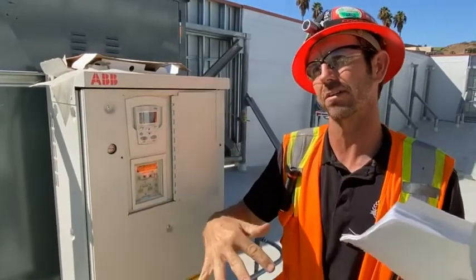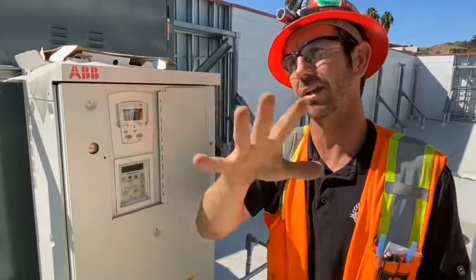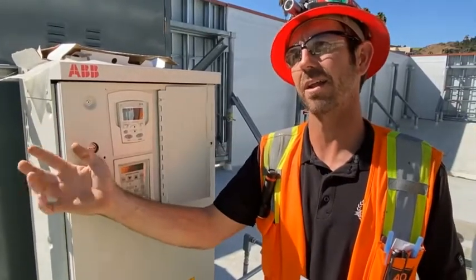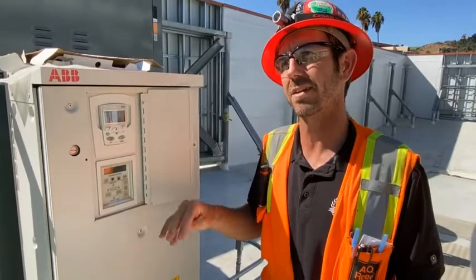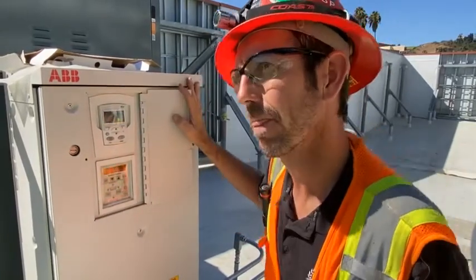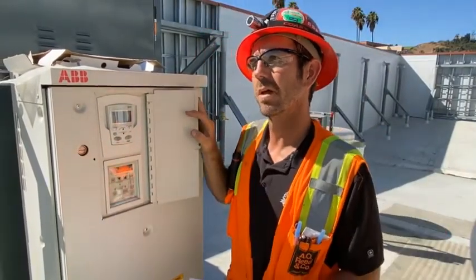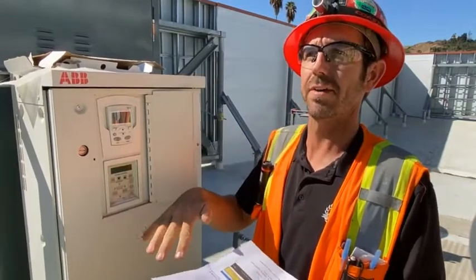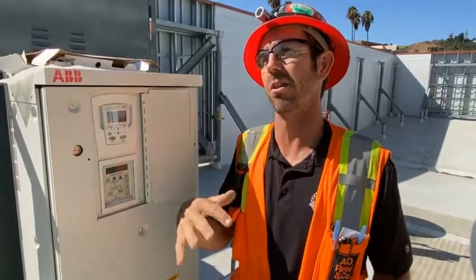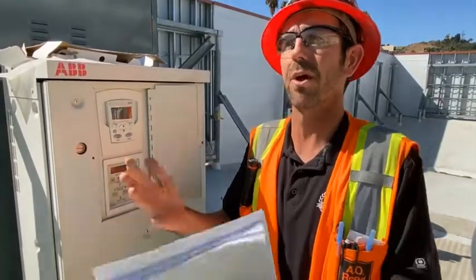You'll start lowering your CFM through the hood, but at that point you need to clean the grease traps, not speed up the fan. Does that make sense? Yeah. The reason you've got a VFD on it is so you can vary your frequency drop. If it just had a starter, like you'll see tomorrow, a lot of the other fans just have starters, you go and run it at 60 hertz.